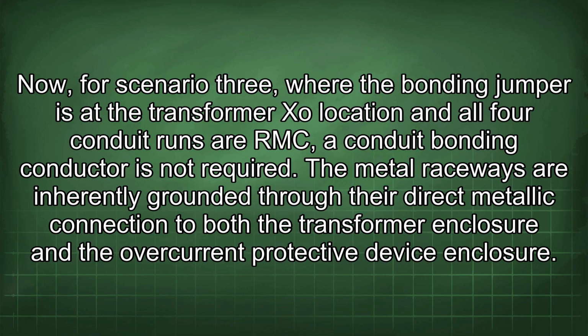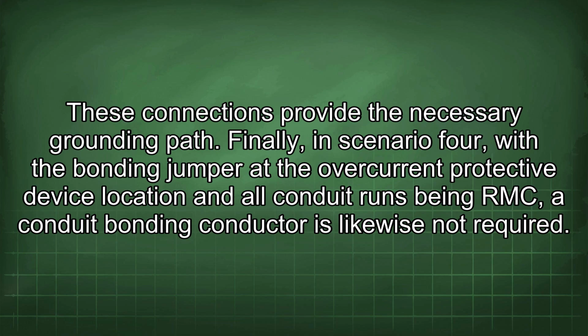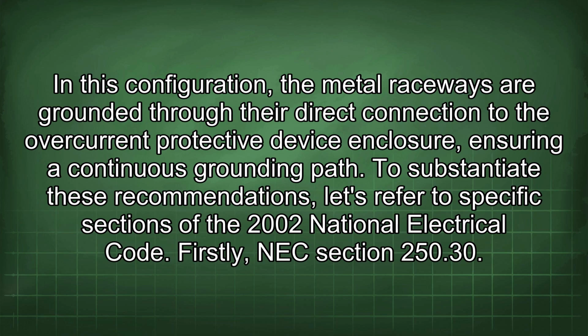Now for Scenario 3, where the bonding jumper is at the transformer XO location and all 4 conduit runs are RMC, a conduit bonding conductor is not required. The metal raceways are inherently grounded due to their direct metallic connection to both the transformer enclosure and the overcurrent protective device enclosure. These connections provide the necessary grounding path. Finally, in Scenario 4, with the bonding jumper at the overcurrent protective device location and all conduit runs being RMC, a conduit bonding conductor is likewise not required. In this configuration, the metal raceways are grounded through their direct connection to the overcurrent protective device enclosure, ensuring a continuous grounding path. To substantiate these recommendations, let's refer to specific sections of the 2002 National Electrical Code.